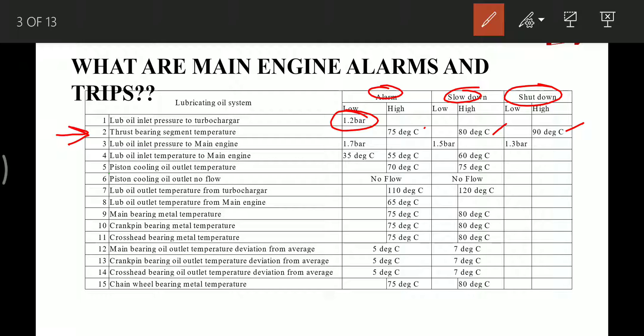Lube oil inlet pressure to main engine: 1.7 bar is the low-low pressure alarm, 1.5 bar is the value for slowdown, and 1.3 bar is the value for shutdown. These alarms and trips are very important as they provide alarm, slowdown, and shutdown — all three.